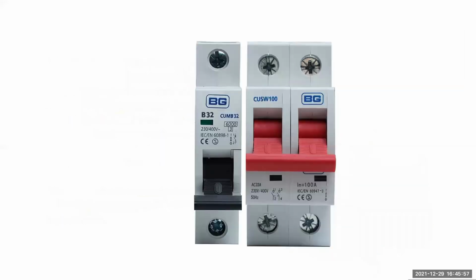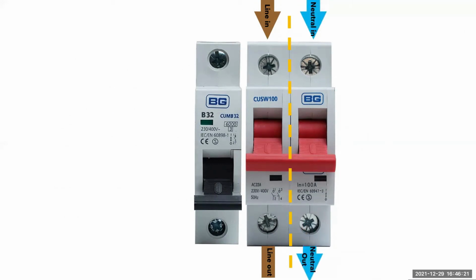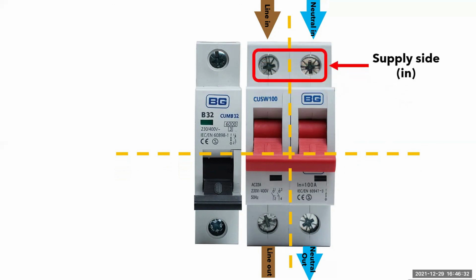The last thing that I want to talk about is the supply side and load side of the main switch and MCB RCBOs. If we divide the main switch down the middle vertically, you will see that the line coming out of the top is the line coming out of the bottom. The same is for the neutral and demonstrates that the switch is straight through. They do not cross over. Then if we divide the switch in half horizontally, you can see that the top of the switch is the supply side in and the bottom of the switch is the load side out.